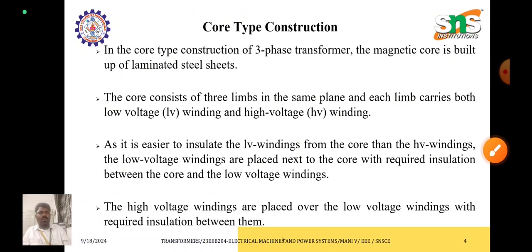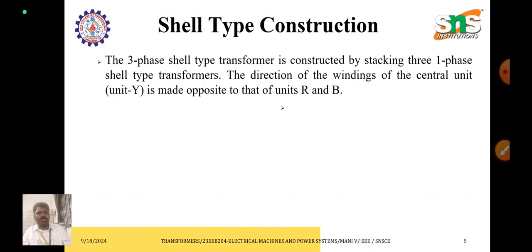In a core type three-phase transformer, the magnetic core is built up of laminated steel sheet. The core consists of three limbs in the same plane. Each limb carries both the low voltage winding as well as the high voltage winding, that is, the primary as well as the secondary winding. As it is easier to insulate the low voltage winding from the core than the high voltage winding, the low voltage windings are placed next to the core with the required insulation between the core and the low voltage winding.